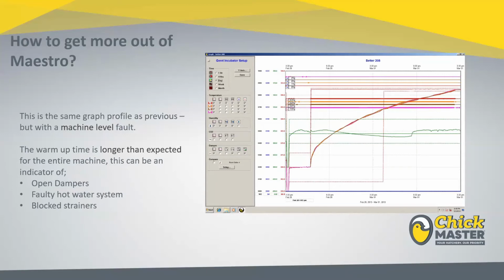If you have a single stage incubator that uses hot water as warm-up, you may find faults in that hot water system, or you may have a blocked strainer with that hot water system that's not allowing adequate hot water flow through the machine in order to help warm up the machine. And this is what we refer to as a machine level fault, not a zonal fault. But it's always a great idea to look at your machines every time they do a warm up and get a good known graph of what it's supposed to be.